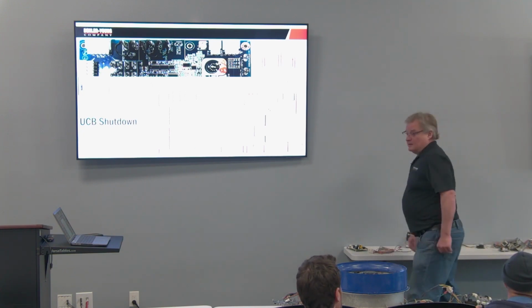Is it clear that he's talking about units that have 2 of these blue axles? No, not just 2. The larger ones, 2. The single ones do as well. So the 7.5 ton and up have the safety circuit. Now, what Dave is saying, this is a 2-blower unit, so it shows a 2, but the other larger ones will still have the 2 red wires just to the 1 motor.